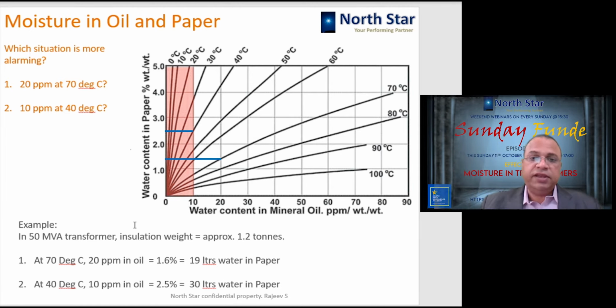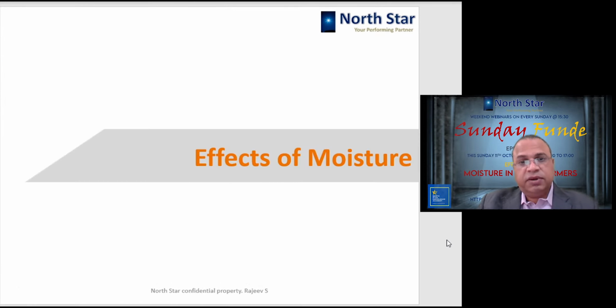Further, I am elaborating here in this example. A 50 MVA transformer is having around 1.2 tons of insulation. So in the first condition, if we look at, this will have around 19 liters of water in paper. And the second condition, at 40 degrees centigrade 10 ppm, will have 30 liters of water. Though the ppm is 10 only, the water in the paper is 30 liters. So this is how the situation should be understood as far as moisture in the oil sample or paper is concerned.